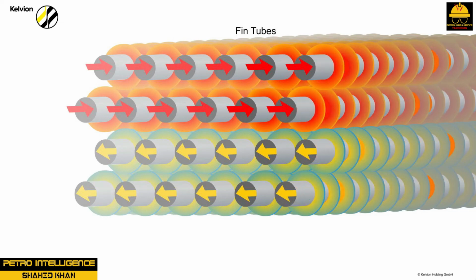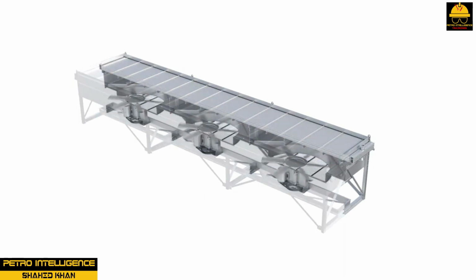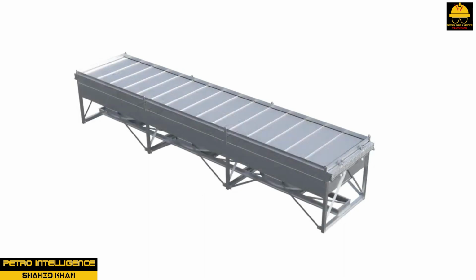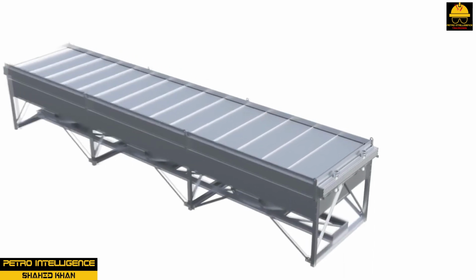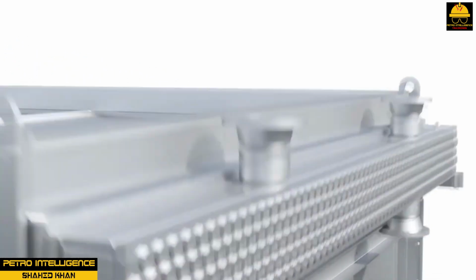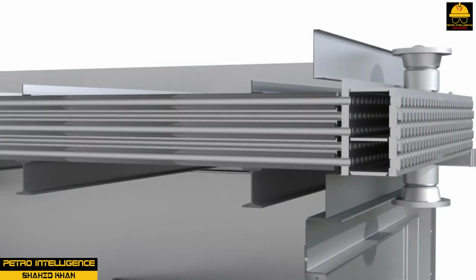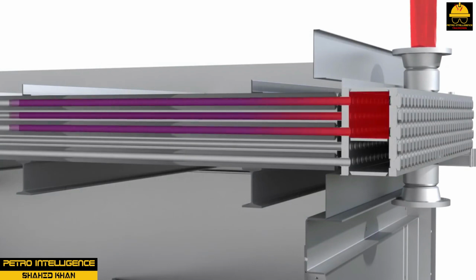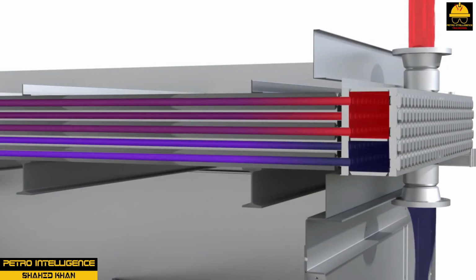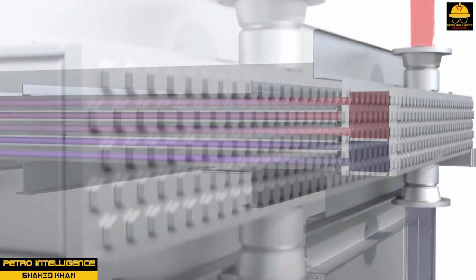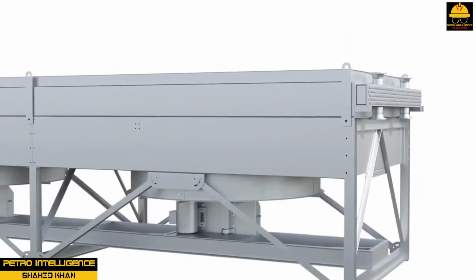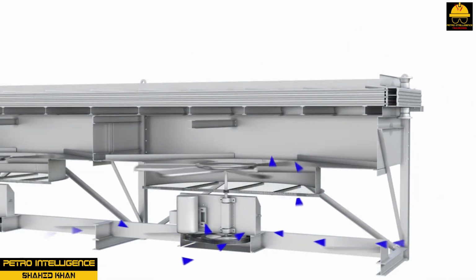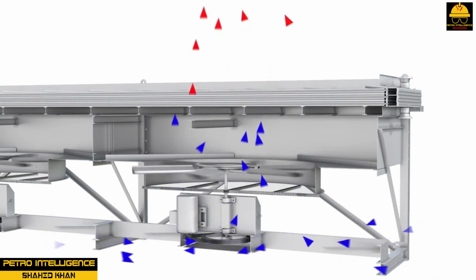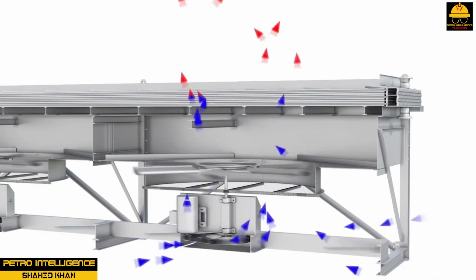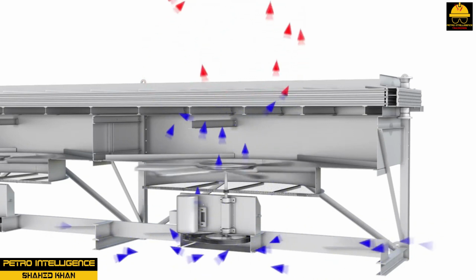Common drivers found in service with air-cooled heat exchangers include electric motor and reduction gears, steam turbine or gas engine, belt drives, and hydraulic motors. The fan blades are composed of aluminum or plastic. Aluminum blades are designed to operate in temperatures up to 300 degrees Fahrenheit or 148.88 degrees Celsius, whereas plastic blades are limited to air temperatures between 160 degrees Fahrenheit and 180 degrees Fahrenheit, or 71.11 degrees Celsius, 82.22 degrees Celsius.